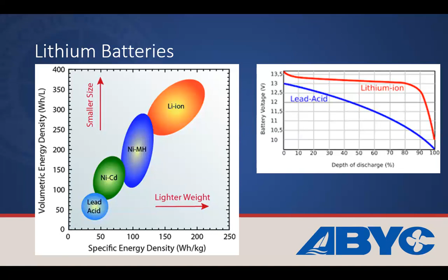It has such a flat discharge and then suddenly drops off at the end, as well as the high end. So you need to make sure you have a shunt in there that basically measures what's going in and out of that battery to establish what its state of charge is.